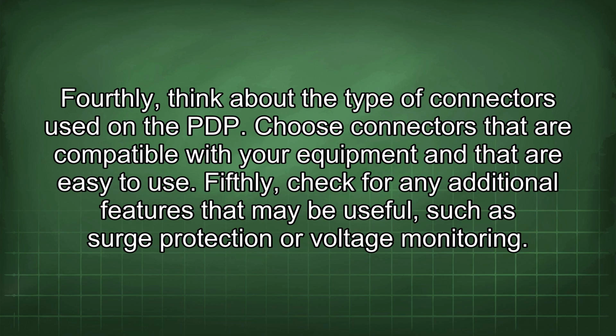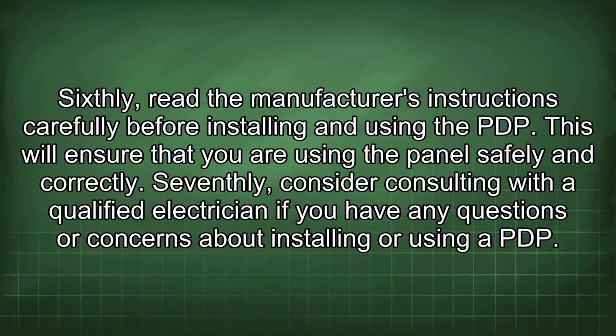Fourthly, think about the type of connectors used on the PDP. Choose connectors that are compatible with your equipment and that are easy to use. Fifthly, check for any additional features that may be useful, such as surge protection or voltage monitoring. Sixthly, read the manufacturer's instructions carefully before installing and using the PDP. This will ensure that you are using the panel safely and correctly. Seventhly, consider consulting with a qualified electrician if you have any questions or concerns about installing or using a PDP.